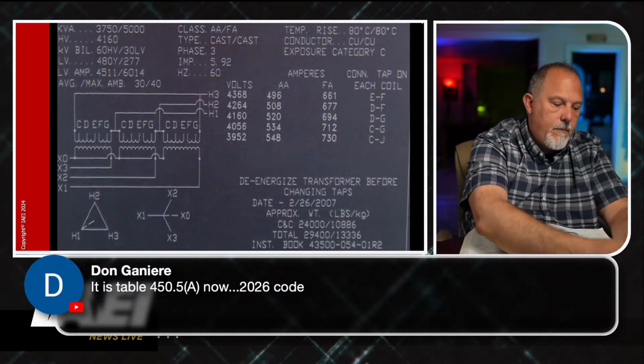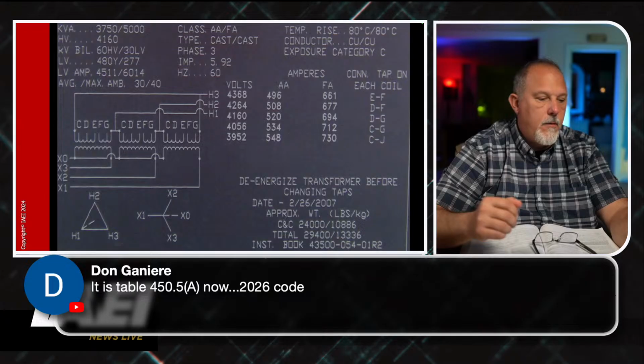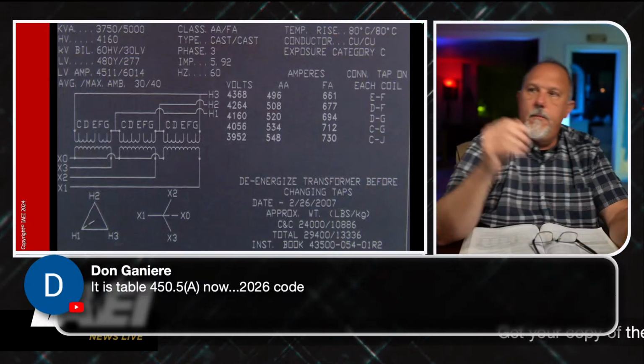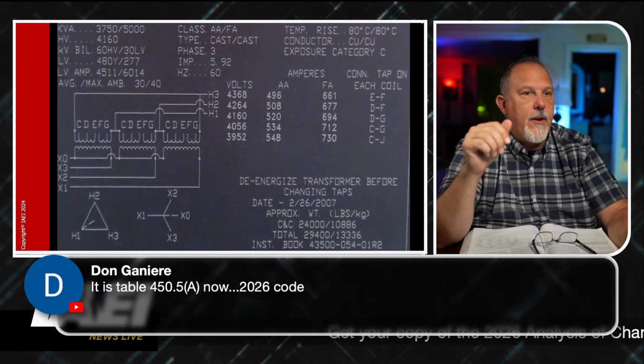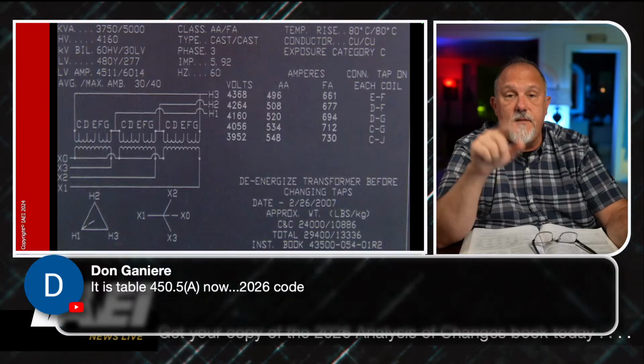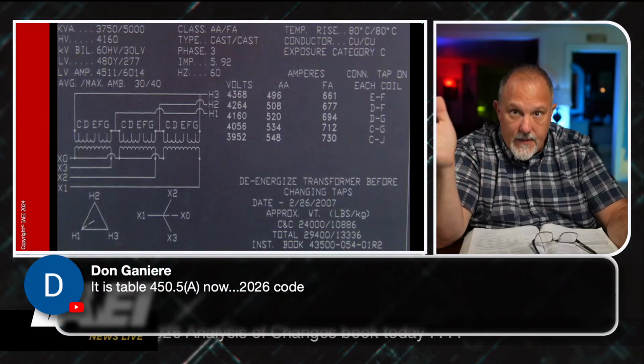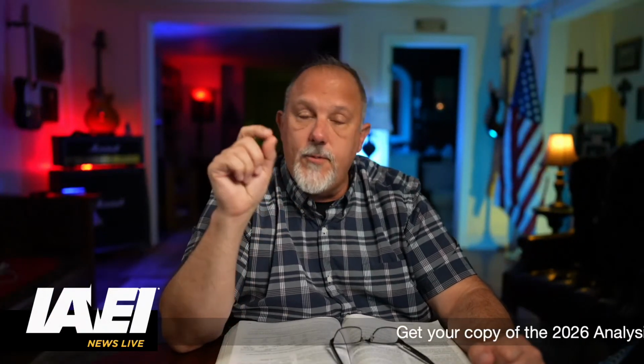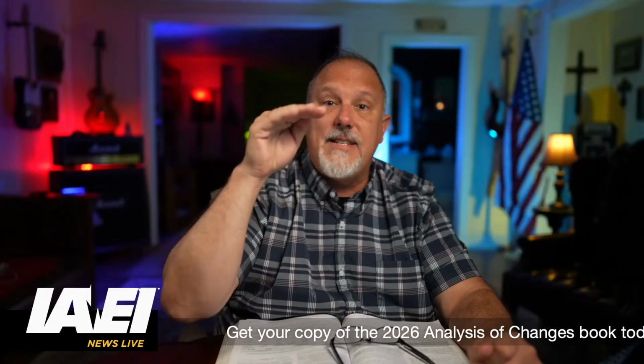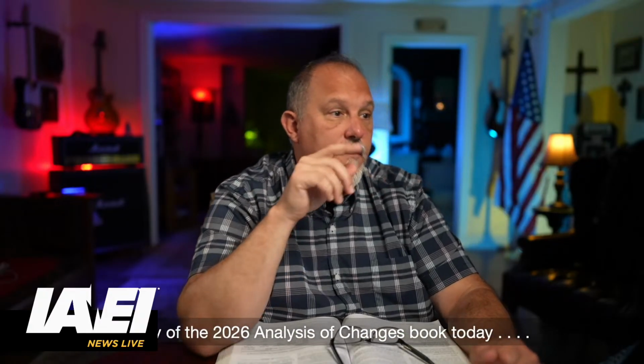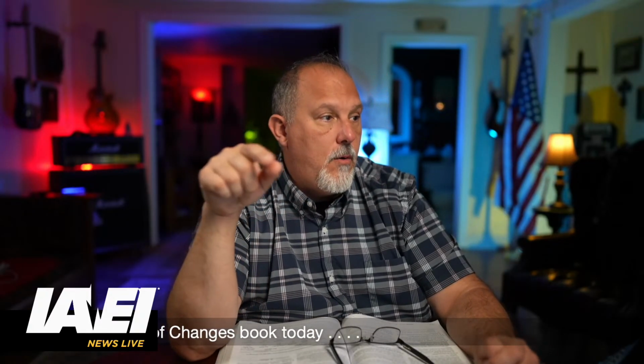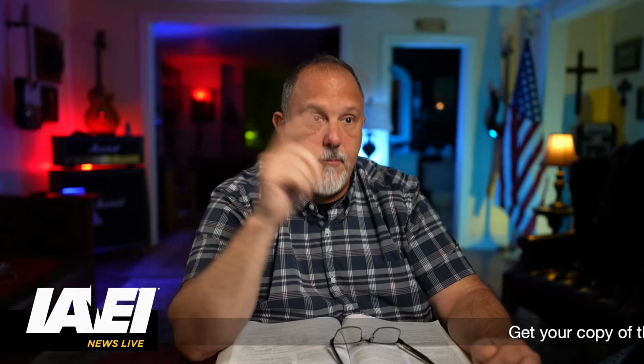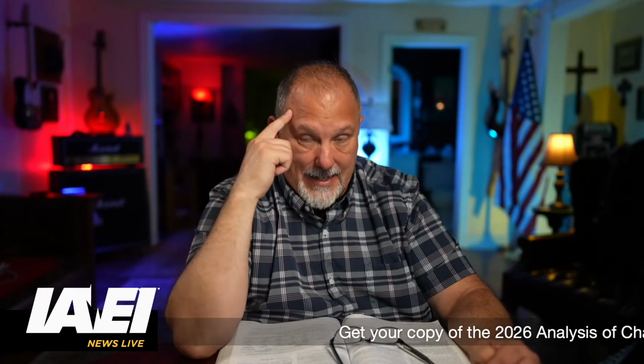the voltage on the secondary. I'm at 480 volts, so it tells me for a 480 volt, in this case 480 volts, the table's telling me I can go up to 125% with the same thing. So for 1,000 volts and below, the next higher amp standard rating or setting for fuses and circuit breakers is permitted above the 125% on the secondary.